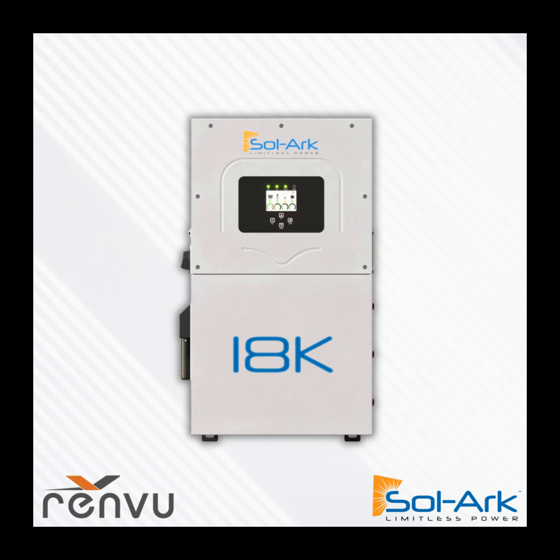Trying to explain commercial design in a short period of time is very hard. But one thing I have to say is that whether it's peak shaving, time of use metering, or VPP, what I see is the same design result: a solar array that minimizes exporting solar power to the grid. That means the solar array might not be larger than the facility load. So when you're designing your solar array, you want to look at your building peak load, and then design a solar array that'll go right up to that peak load, but not larger than it.